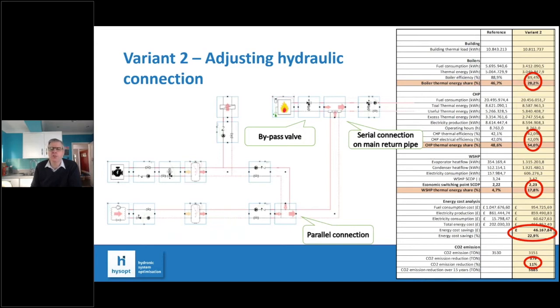Again, different hydraulic integrations of the plant, and you can see the impact that has. Now we're really starting to increase the heat pump share to about 18%, and reducing the boiler share down to less than 30%. We've made about a 23% saving in energy costs and an 11% saving in carbon. We haven't changed the boilers, it's the same plant - all we've done is change the way they're hydraulically linked together.